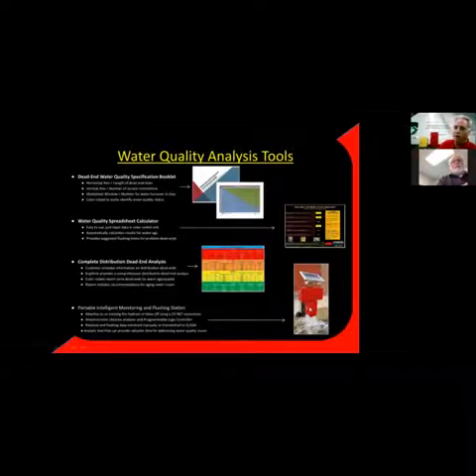At the scheduled time, the device turns on, flushes some water to get flow going, the flow cell opens, it takes a sample, and measures the chlorine. If it's below 1.0, it will flush the exact amount of water until it hits 1.5, while capturing all the data. It has an RV-50 wireless gateway transmitter that sends data right to your phone, laptop, or SCADA system. I can have up to eight sensors — chlorine, pH, PSI, temperature, turbidity, ORP, and others.